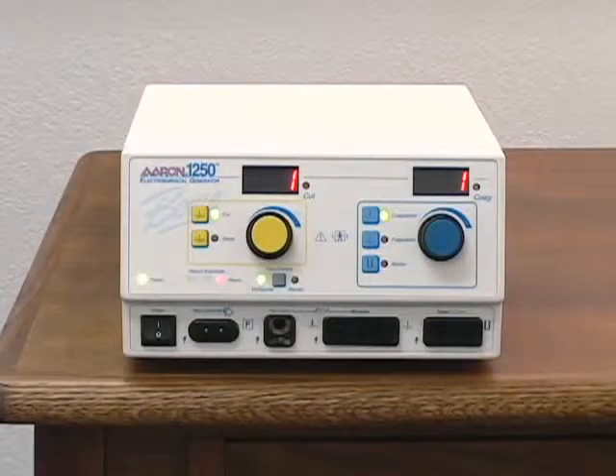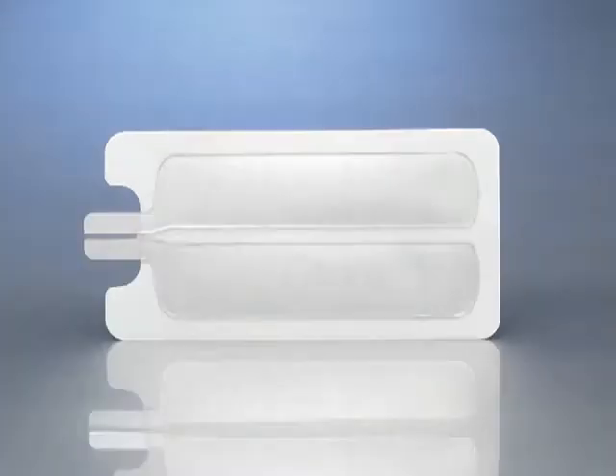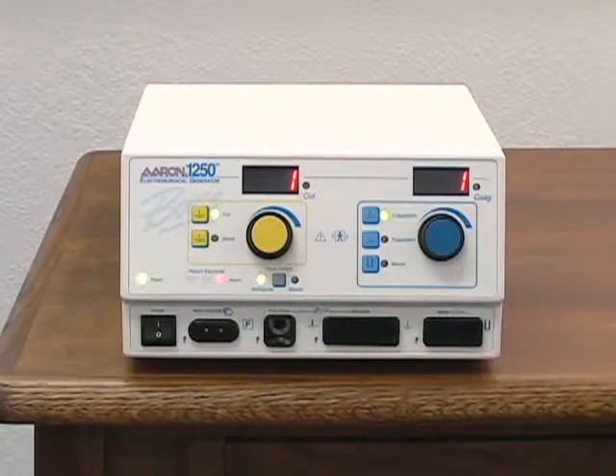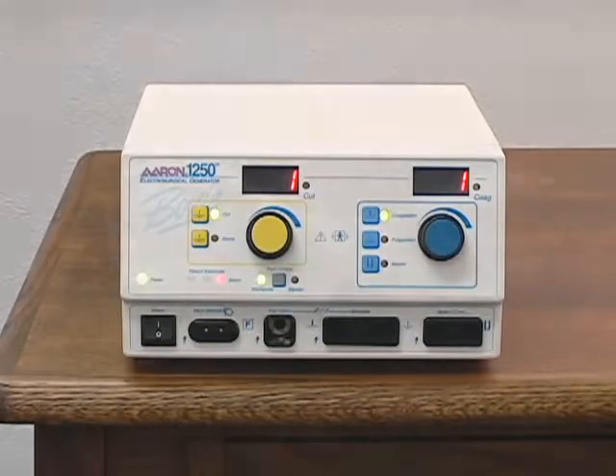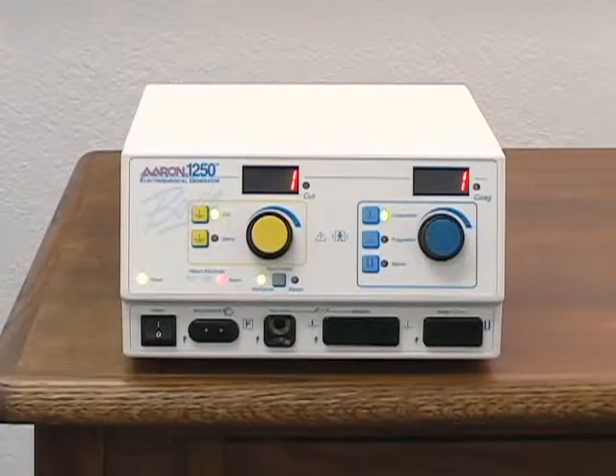The AARON 1250 is an isolated unit, and all monopolar modes require the use of a grounding pad. Grounding pads are available in a variety of configurations: solid pad only, solid pad with attached disposable cable, split pad only, and split pad with attached disposable cable. Pads without cables are to be used with the reusable grounding cable. The AARON 1250 is packaged with a reusable grounding cable and five disposable split pads.